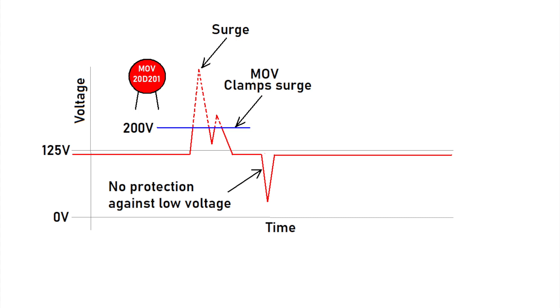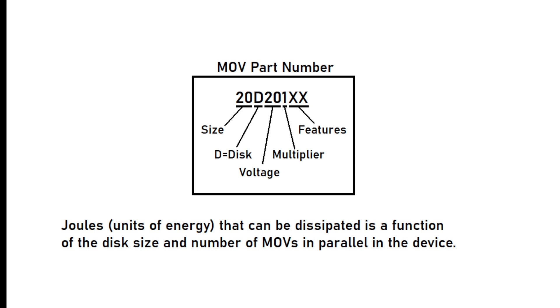However, MOVs do not protect against low voltage conditions. And, as you may expect, the MOVs are available in a wide range of voltages and the energy that they can dissipate. As well, MOVs can be wired in parallel to increase the energy dissipation capability.